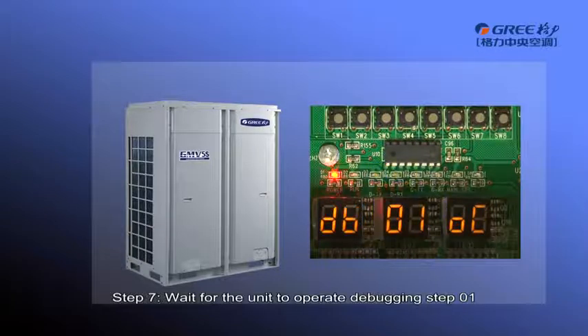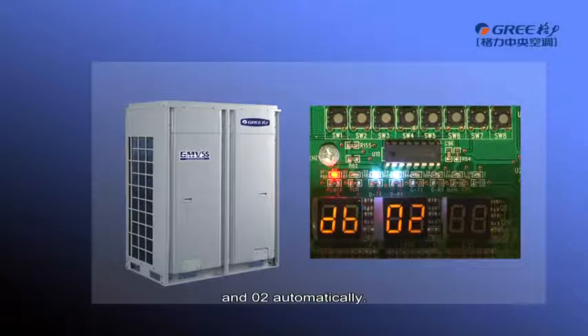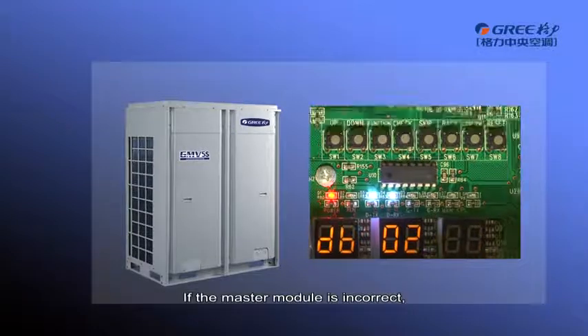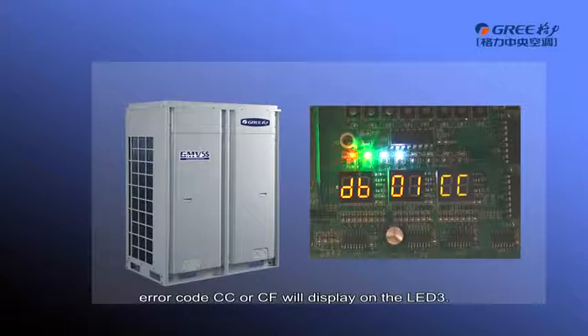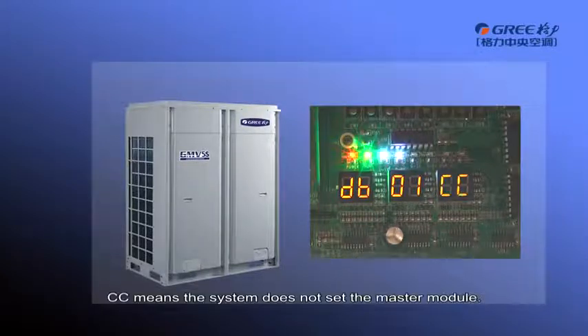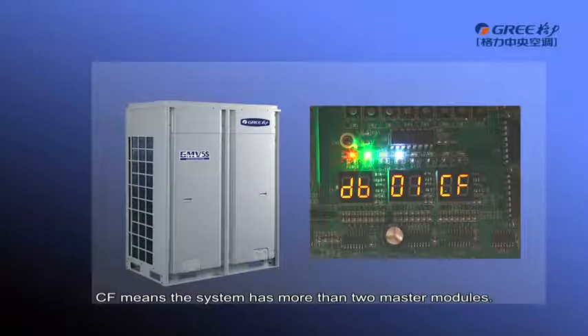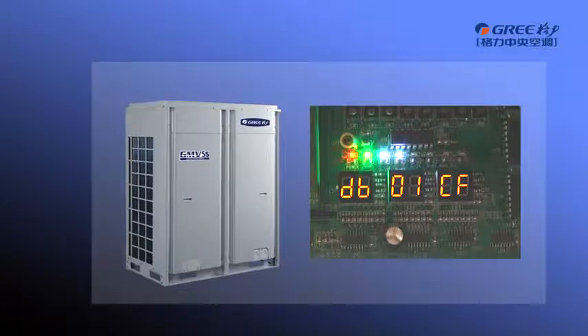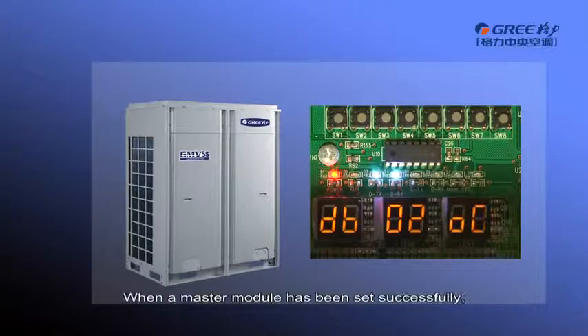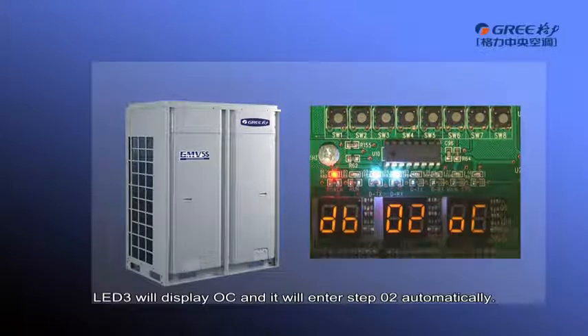Step 7. Wait for the unit to operate debugging step 1 and 2 automatically. If the master module is incorrect, error code CC or CF will display on the LED 3. CC means the system does not set the master module. CF means the system has more than 2 master modules. When the master module has been set successfully, LED 3 will display OC and it will enter step 2 automatically.